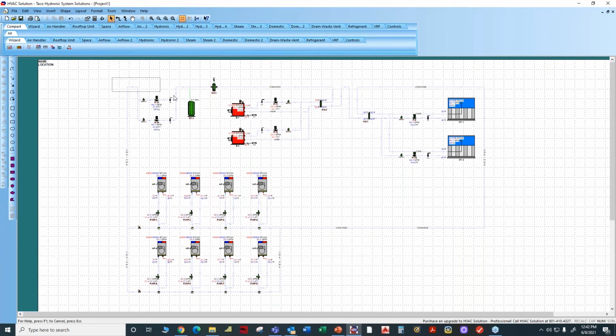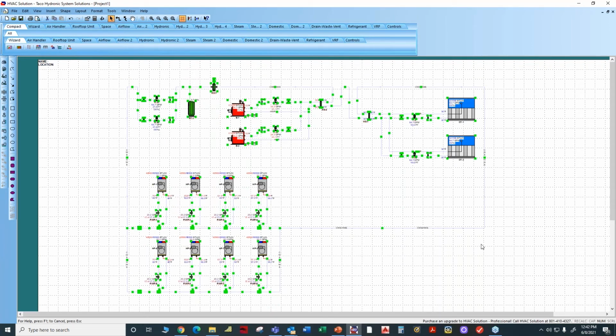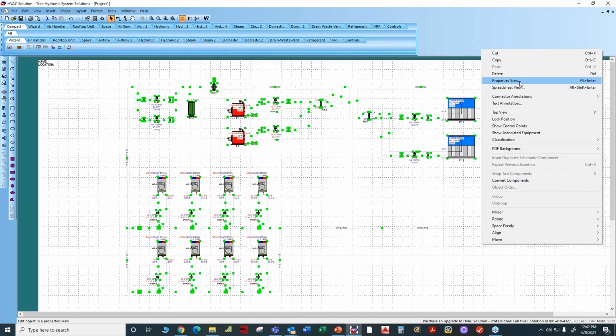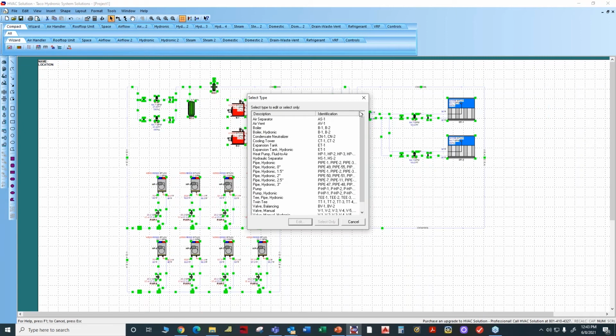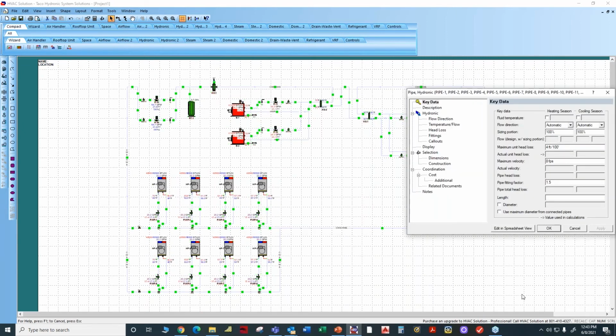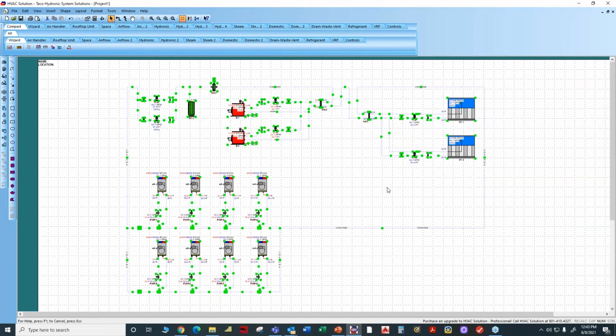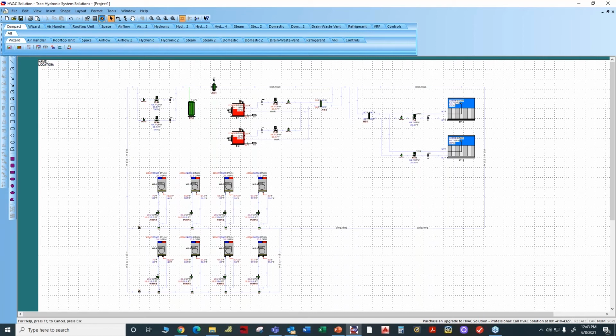So, to give the pumps a little bit of resistance to overcome, I'm going to just arbitrarily, just for our discussion today, take the hydronic pipe and say each section of pipe is going to be 20 feet. Now, it's a little bit bizarre, but I want something in there for pipe length so that it'll calculate some pressure drop. So I'm going to go over here and do some selection, and hopefully that worked. Yep. Okay, so now we have a conventional system. In the previous discussion, it was an air to water heat pump, and this is the opposite. This is a water to air heat pump system, or sometimes referred to as a water source heat pump system.